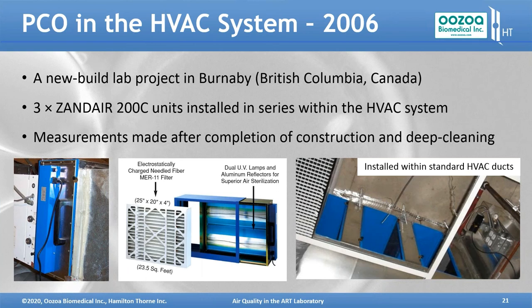And you can see on the right here, the picture of these three, these are the outside blue cases for the units before the units themselves were actually installed, and power was provided and whatever. So we had three in direct series in the return air, because in the return air the air velocity is lower, so there's more dwell time, so there's better performance of the units. And we made measurements of VOCs after completion of construction and deep cleaning of the new facility.